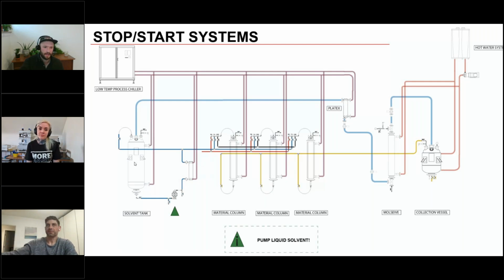As you drain the tank out, you're lowering and maintaining a lower pressure in your solvent tank, pumping it through your column and into your collection pot, where it hits the hot surface, increases pressure, and wants to go back to the low pressure zone. You get a system that goes faster and faster as it runs, because as you're condensing passively, you're cooling your solvent tank and lines down, creating a continuous system with no breaks. We're a strong proponent of continuous systems versus stopping and starting, extracting then recovering.